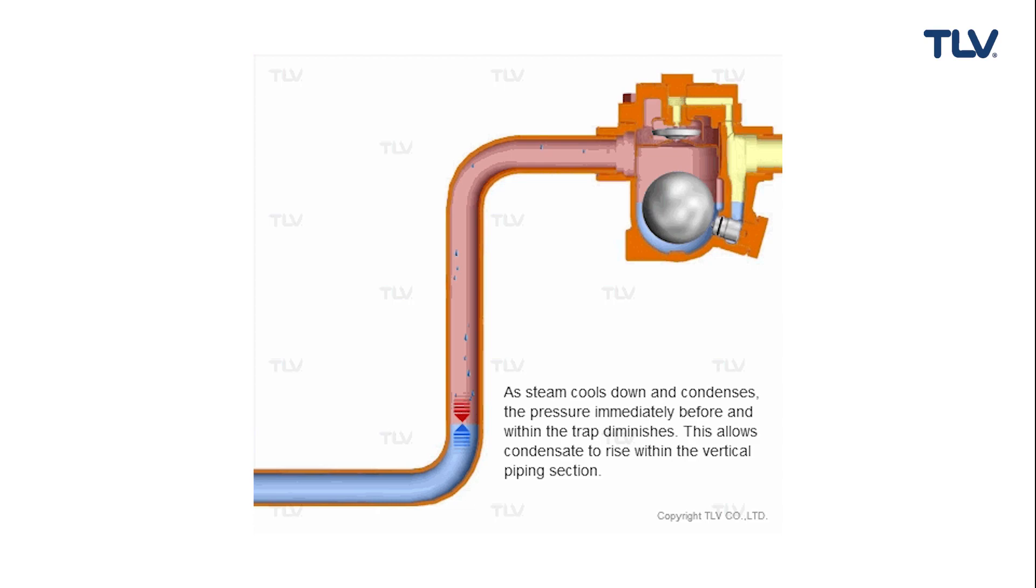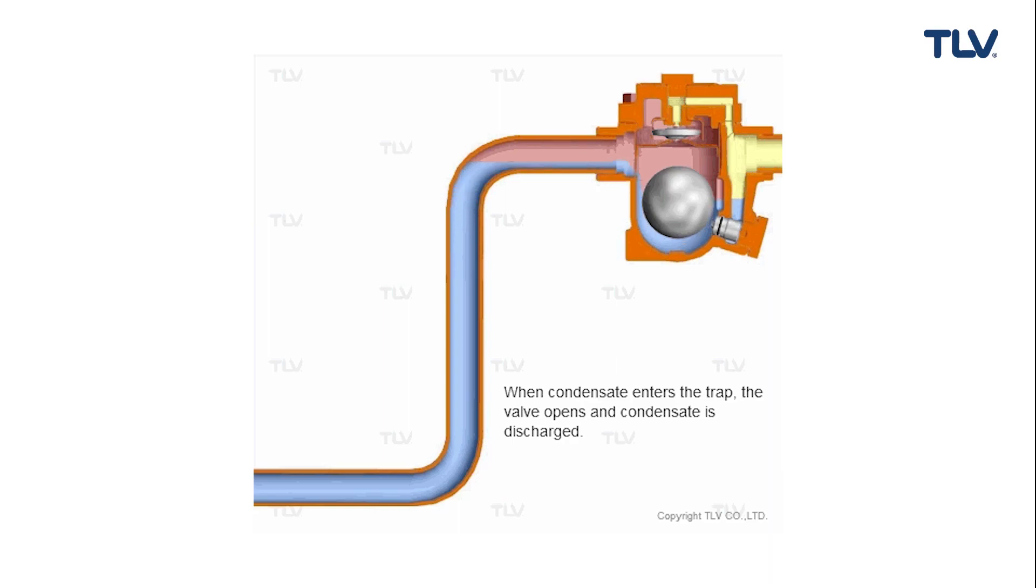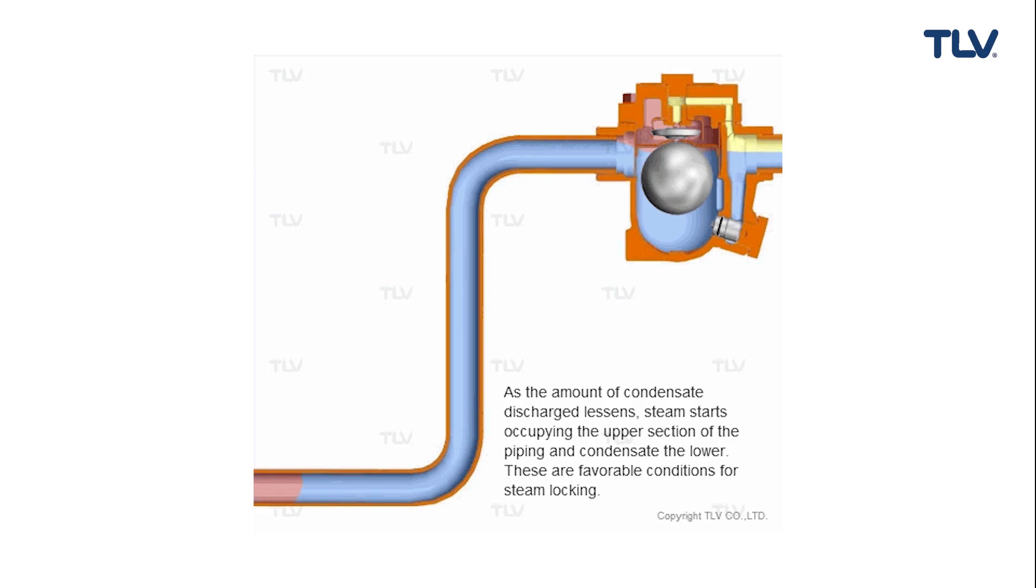A steam locked trap will eventually be able to discharge condensate again when the locked steam has condensed. In the meantime, however, it may cause condensate backup in piping and equipment. If the problem is not resolved, it can then reoccur at every following discharge cycle.